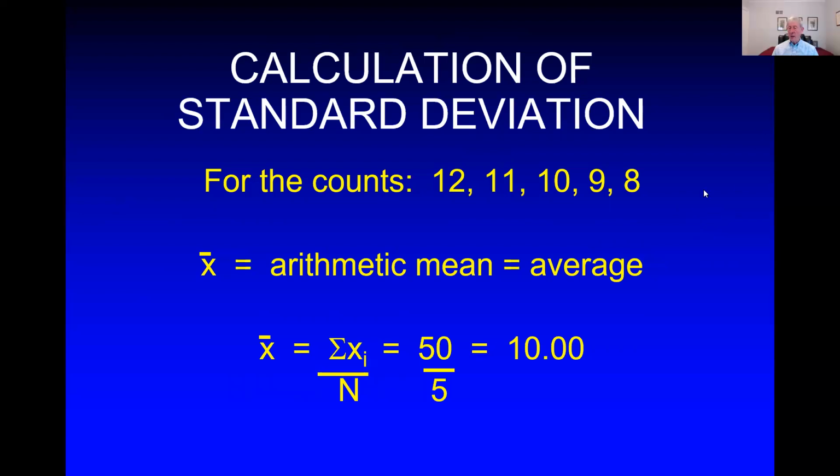That's good. Definitely not. Look, your average value here is 10. These values, 11 and 9, are 10% off. That's already, you're at the legal limit. And 12 and 8 are 20% above and below. This is a terrible dose calibrator. Is it accurate? Yes.